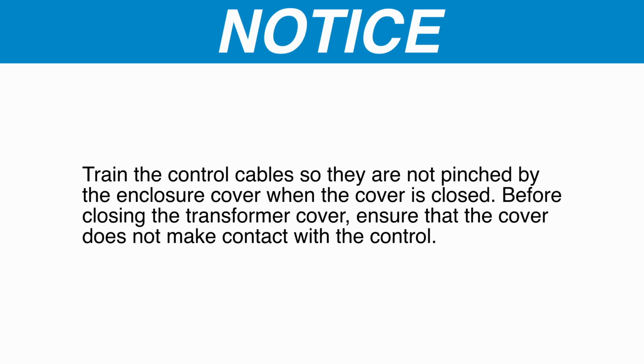Notice, train the control cables so they are not pinched by the enclosure cover when the cover is closed. Before closing the transformer cover, ensure that the cover does not make contact with the control.